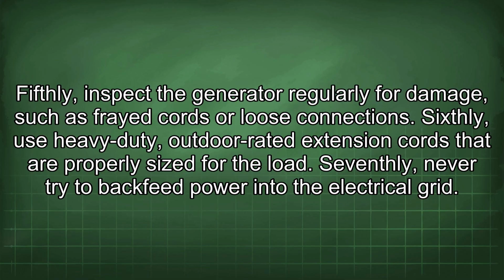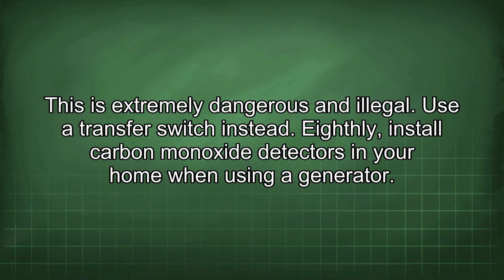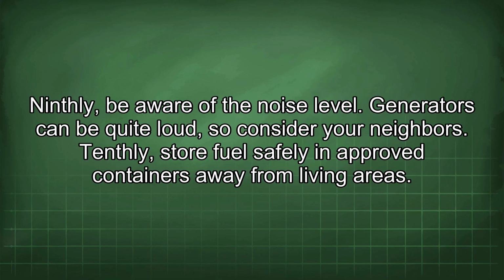Seventhly, never try to backfeed power into the electrical grid. This is extremely dangerous and illegal. Use a transfer switch instead. Eighthly, install carbon monoxide detectors in your home when using a generator. Ninthly, be aware of the noise level. Generators can be quite loud, so consider your neighbors. Tenthly, store fuel safely in approved containers away from living areas.